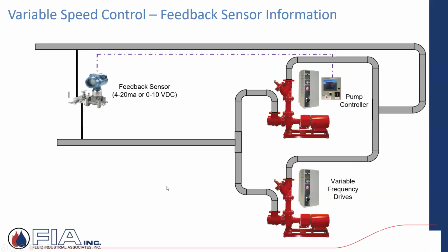Just a quick picture showing some base mounted pumps with some drives, which might be in the mechanical room right next to the pumps, but they have a remote feedback sensor that's measuring supply and return. So here's my distribution, here's my discharge off the pump through my triple duty valve on my supply main going out to the building. Hopefully as far out in the system as I can, I have a supply sensor. I have a sensor on the return that's feeding back to the suction of these pumps. So this is, hopefully, my greater variable head loss that I can take advantage of.